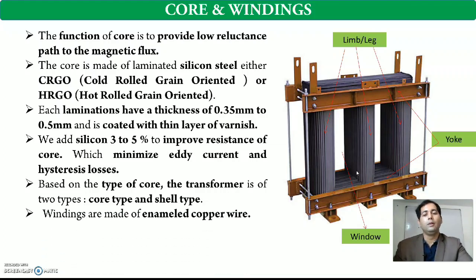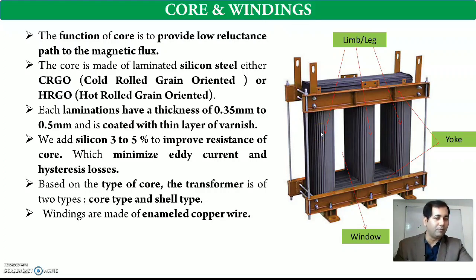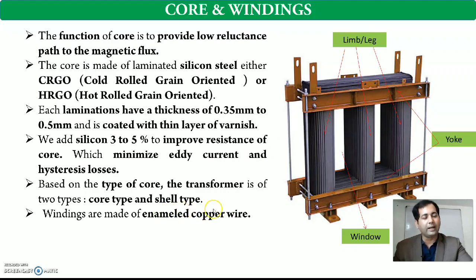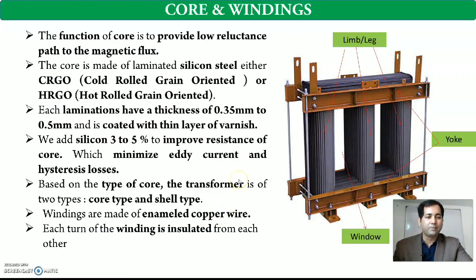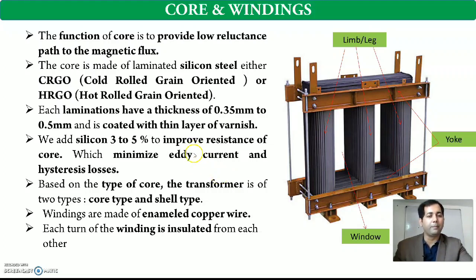The window allows primary and secondary windings to be isolated from each other, and also allows circulating air or oil to flow easily for cooling purposes. Regarding winding: windings are made of either copper or aluminum. For a good quality transformer with low resistivity, we use enameled copper — the copper is insulated to prevent short circuits when mounted. The quality of insulation depends on the voltage rating and size of the transformer. The purpose of winding is to carry and induce current. All windings except in an auto-transformer — primary and secondary — are isolated from each other.